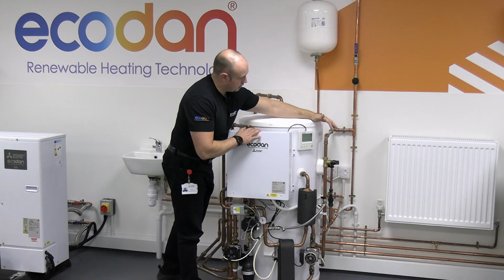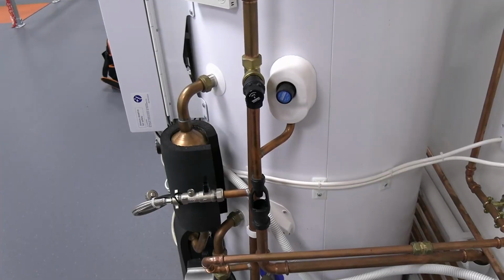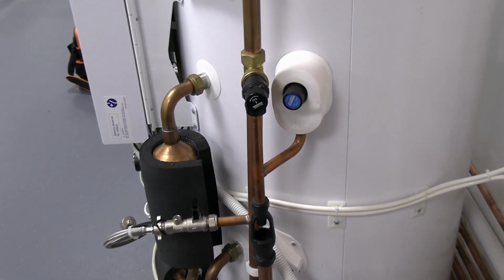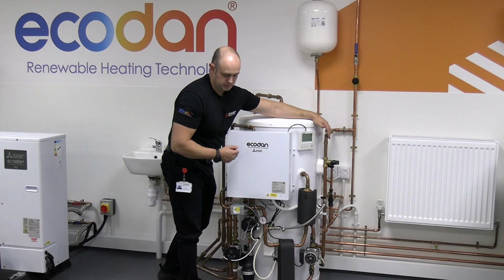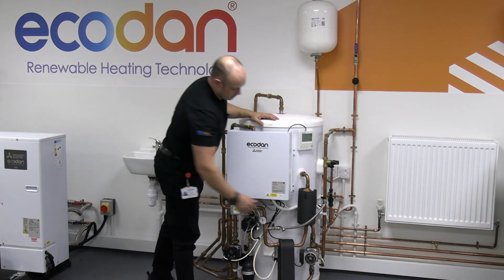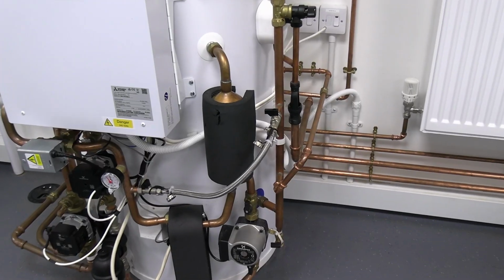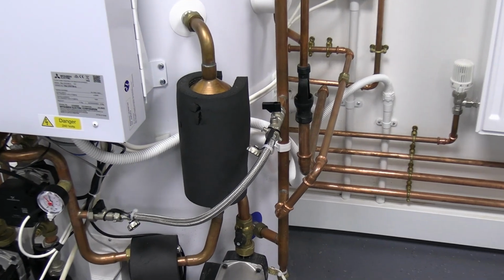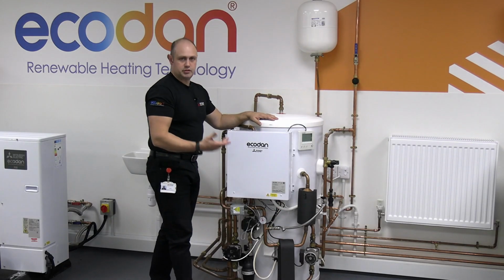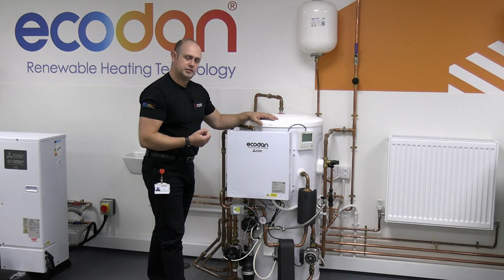On the other side, we've got my safeties. So that's my pressure relief valve, temperature relief valve, and that side of things down to a tundish. I've also got my filling connection on there. Obviously, I've left this in place. In a normal situation, you'd be disconnecting that, but this is a training room, so I'm quite often playing about with the water side in here.